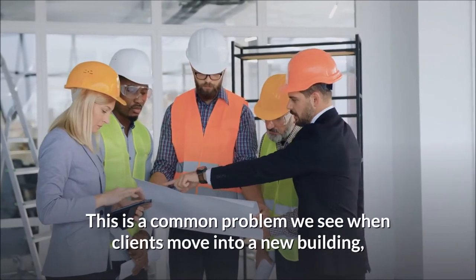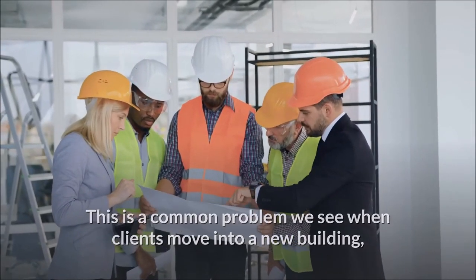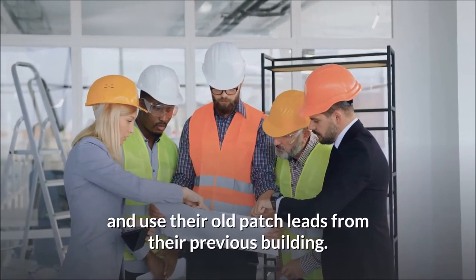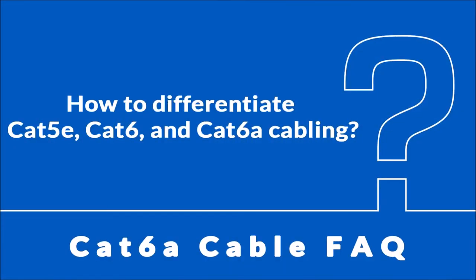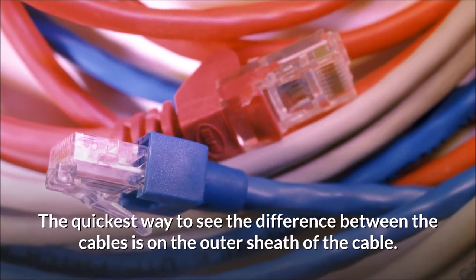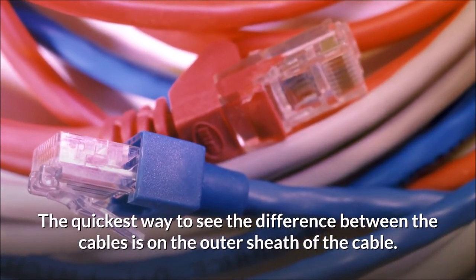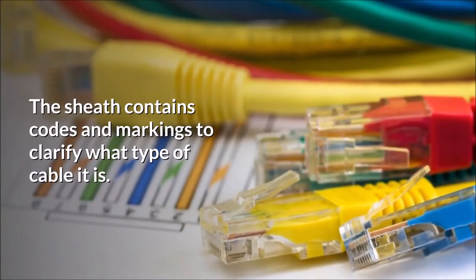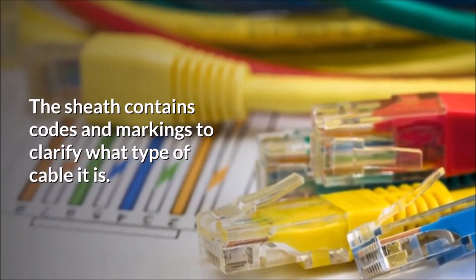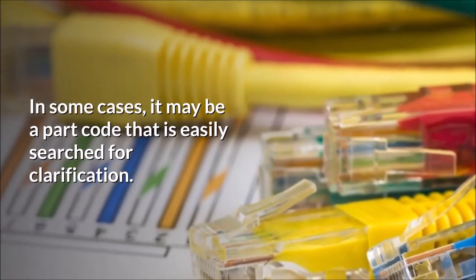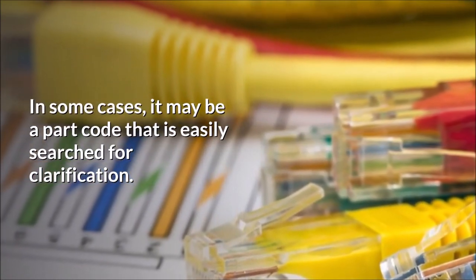This is a common problem we see when clients move into a new building and use their old patch leads from the previous building. How to differentiate Cat5e, Cat6, and Cat6a cabling? The quickest way to see the difference between the cables is on the outer sheath of the cable. The sheath contains codes and markings to clarify what type of cable it is. In some cases, it may be a part code that is easily searched for clarification.